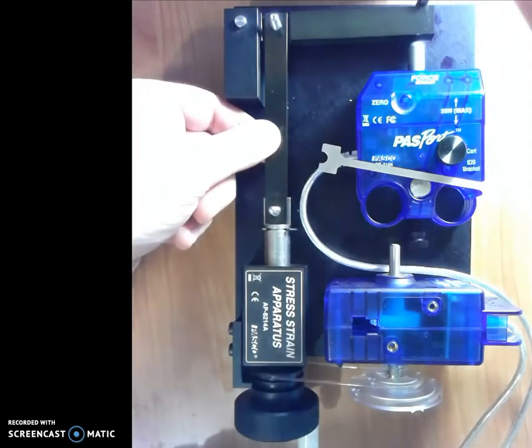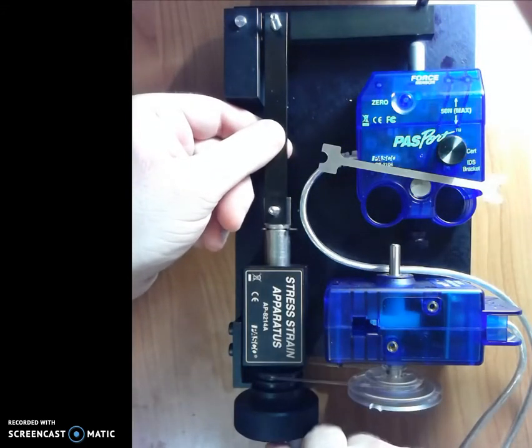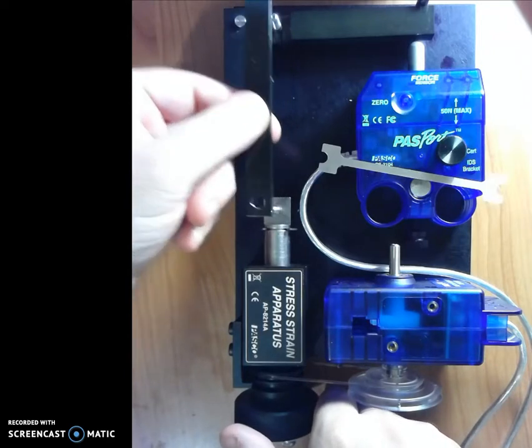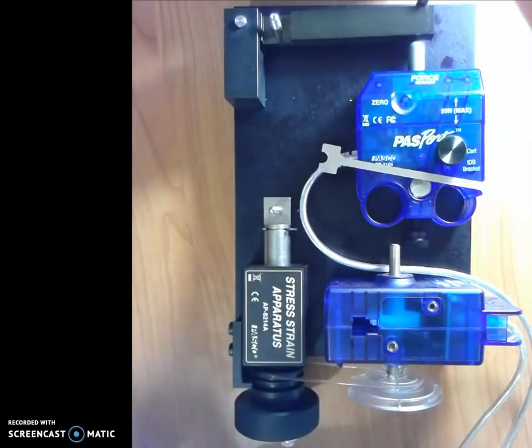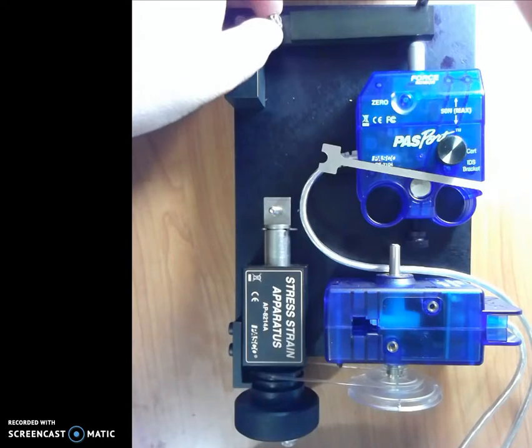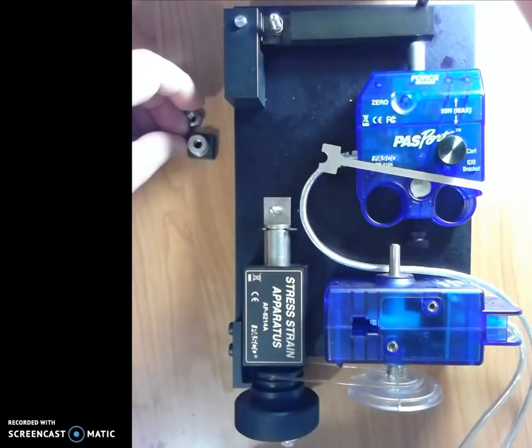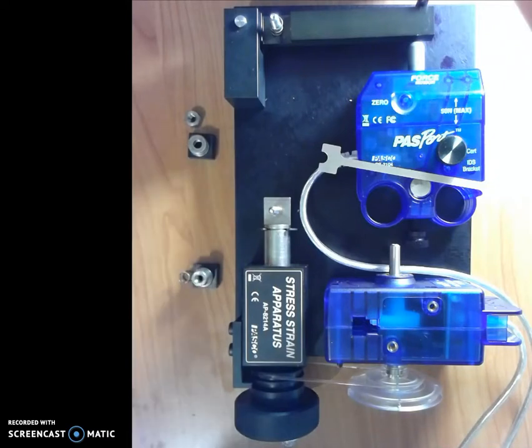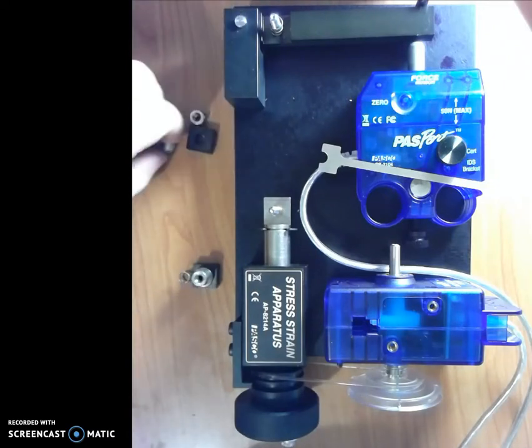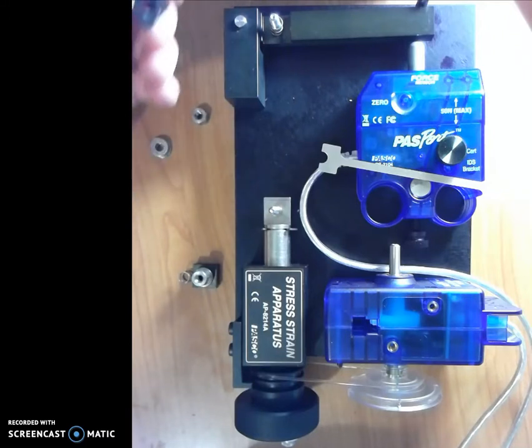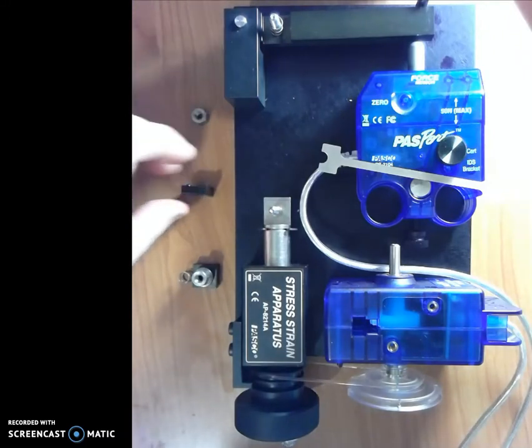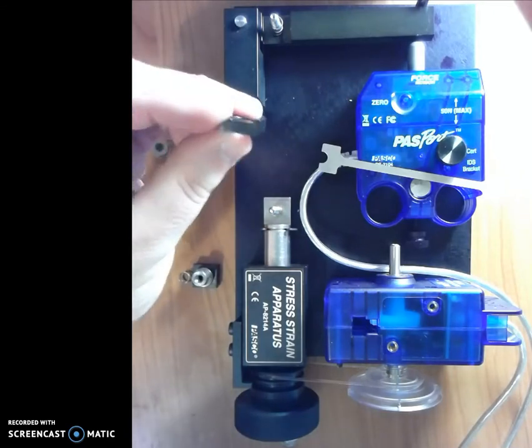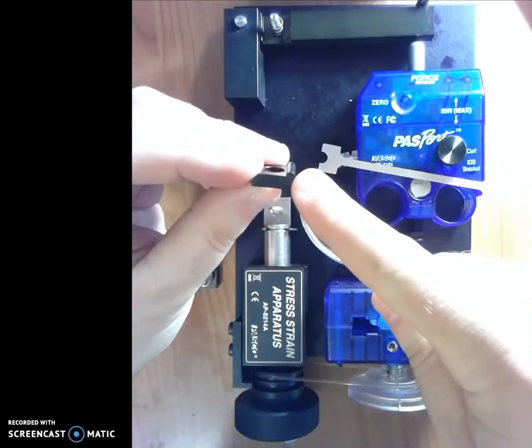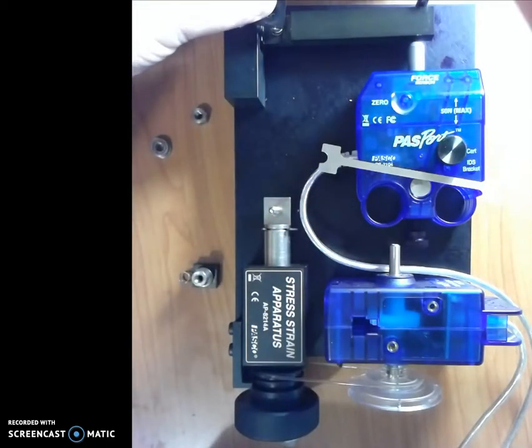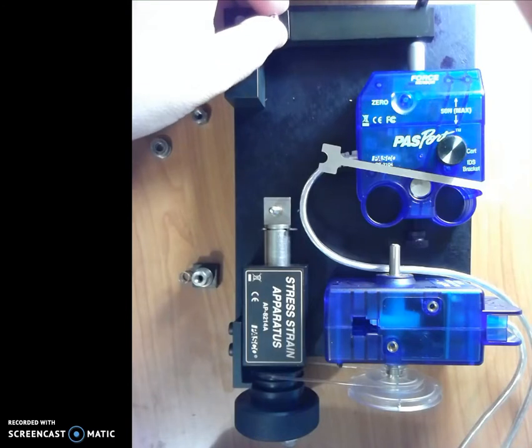I'm going to lift the calibration bar out, and I may need to adjust this so that it's loose. There we go. Okay, it comes out. And then instead of just putting the sample coupon back on, I'm going to put these springs. Remember, I had these components which I pulled off from before, so I'm going to put the spring on. I'm going to put this little clamp on. Now I've got to be very careful with the clamp. Let me set it right here so you can see it. There is a little kind of a lip. See that right there? A little lip. So I want the lip facing forward. That's what's actually going to clamp onto the sample coupon.